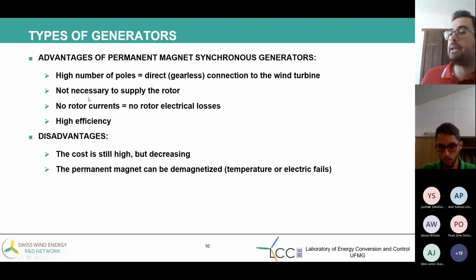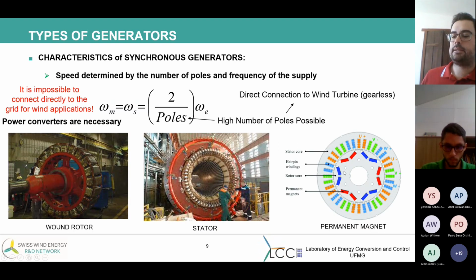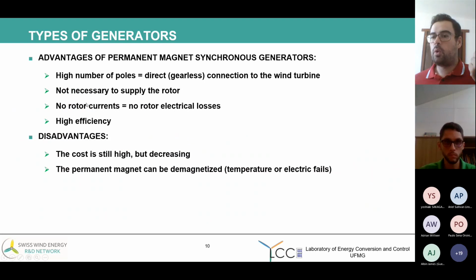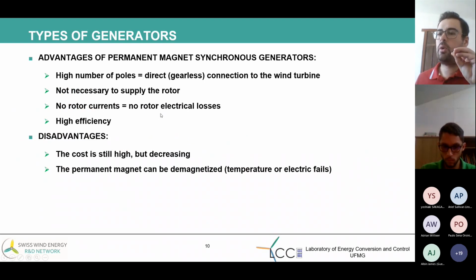It's not necessary to supply the rotor. With the use of permanent magnets, there are no rotor currents, so no rotor electrical losses. Then permanent magnet synchronous generators have high efficiency. The disadvantages are that the cost is still high, but decreasing. For offshore applications, the expansion makes the cost decrease.